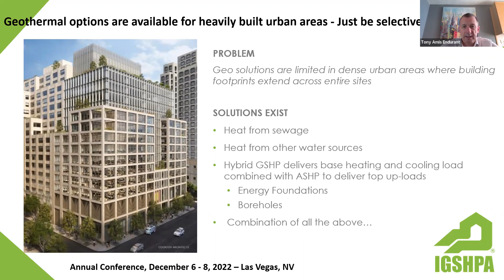Over the last two or three years here in New York, we've done some great studies thanks to NYSERDA PON 4614. We've looked at a multitude of projects - affordable housing, schools, commercial buildings - and one of the things we've looked at on a couple of projects is connecting into existing sewer runs. On one particular project, the adjacent sewer flow rate of between 19,000 and 51,000 gallons per minute was able to deliver the entire peak heating and cooling load for that building. The beauty of this solution is that it's not particularly invasive compared to what a borehole solution might require.